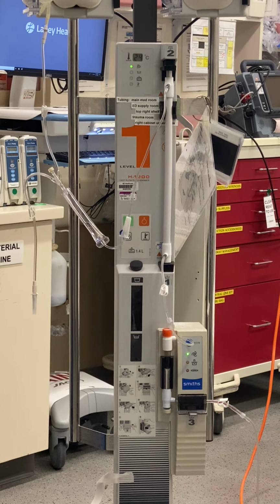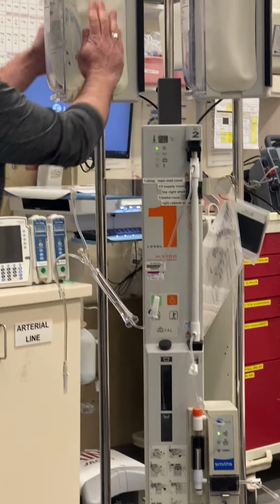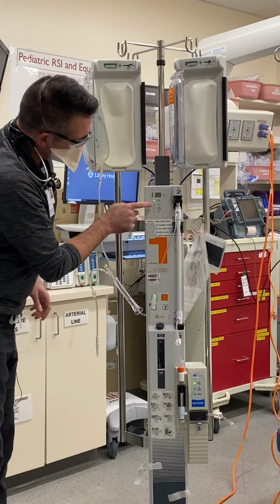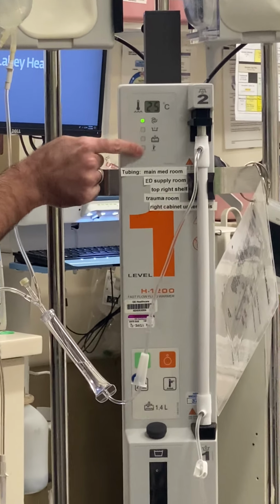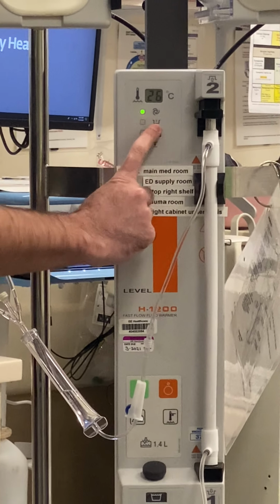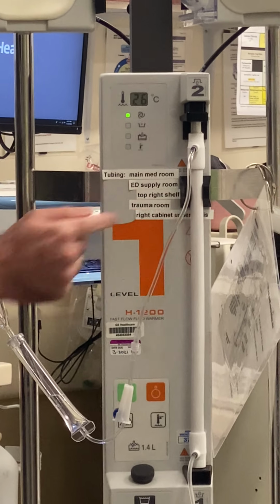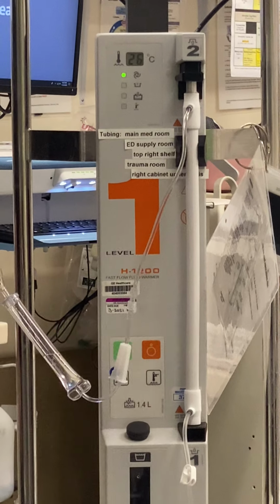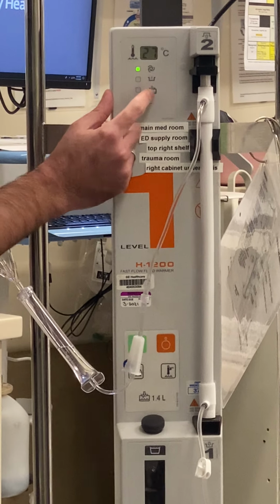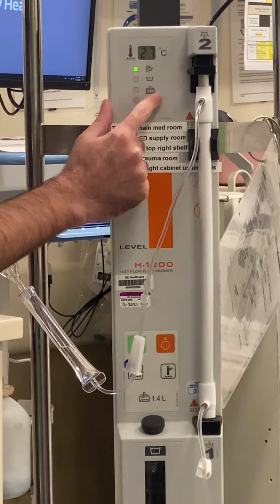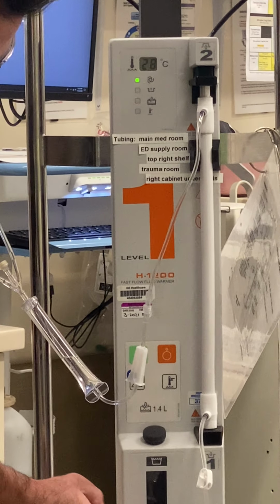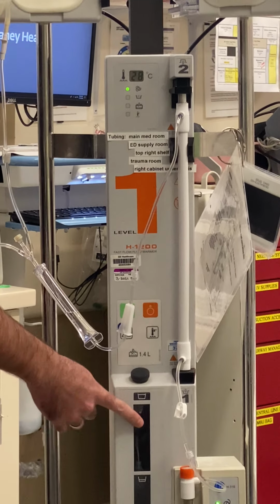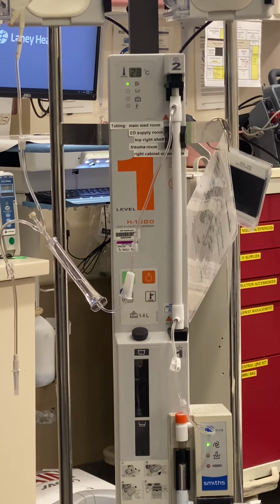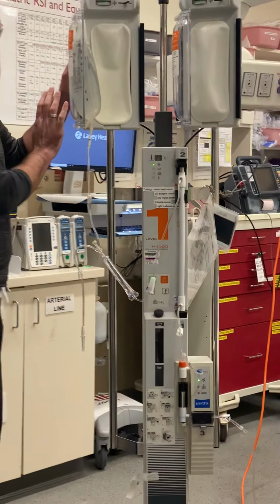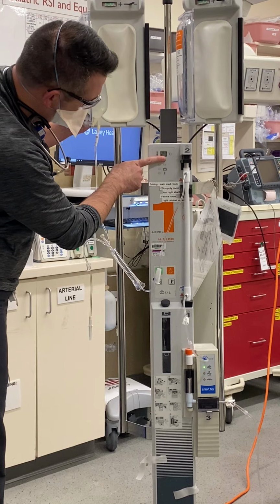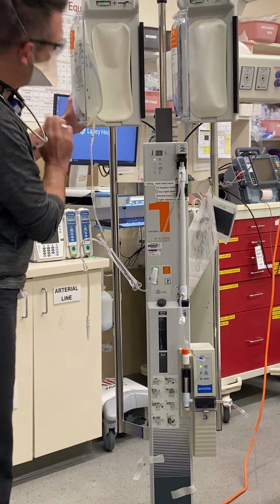We'll go through a bunch of self-checks here. If ever you see these lighted up, this little icon means check disposables, and so that means that you probably didn't put the cartridge in correctly. So check all your connections. This icon here means that there isn't enough fluid inside the reservoir, and it, by the way, is just sterile water. So anyway, if you want to use it, also note the temperature. So we're starting out at 29 centigrade. It will heat up pretty quickly.